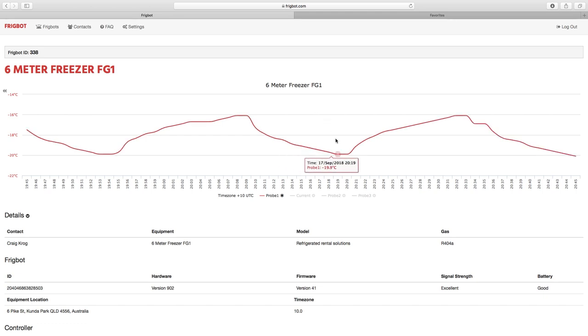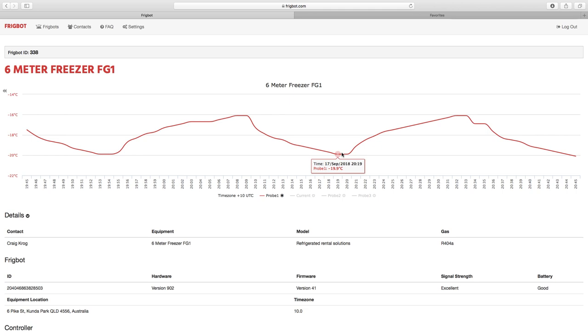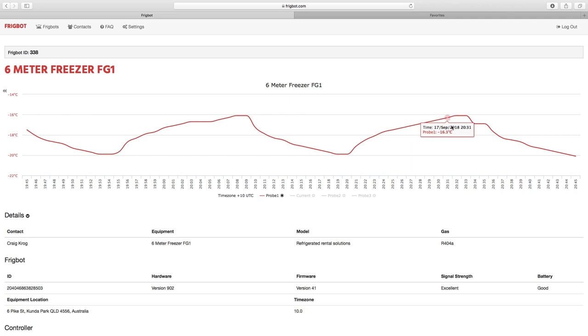So here we can see the room is cutting in and cutting out as it should. It's got a minus 20 degree set point, so it runs down till it gets to minus 20 degrees. It's got a four degree differential, so when it gets up to minus 16 it cuts back in again.